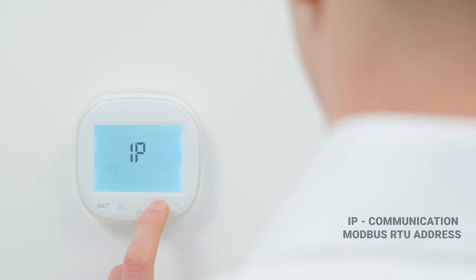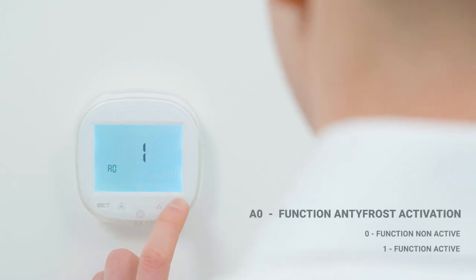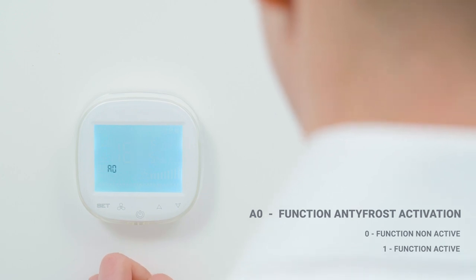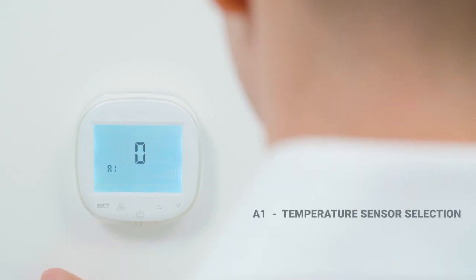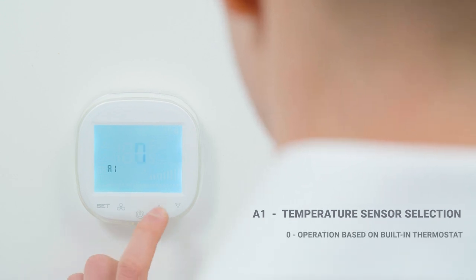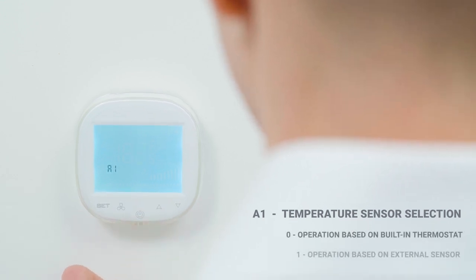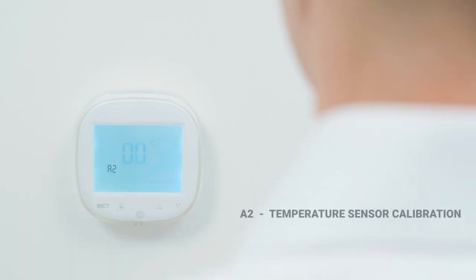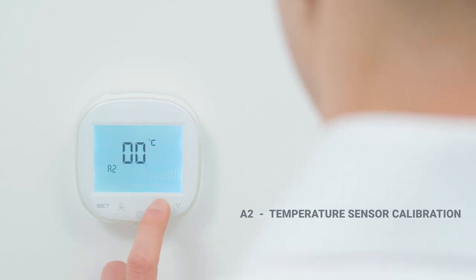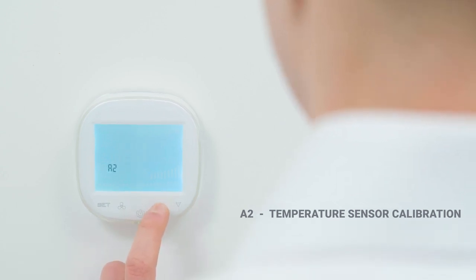The IP function is to change the address assigned to a building management system BMS. Function A0, activation and deactivation of anti-frost function. Function A1, selection of the temperature sensor. Value 0 means operation based on a built-in thermostat. Value 1 means operation based on an external temperature sensor. Function A2, temperature sensor calibration. If the actual room temperature differs from the one indicated by the controller, we can correct the sensor by plus and minus 8 Celsius degrees.